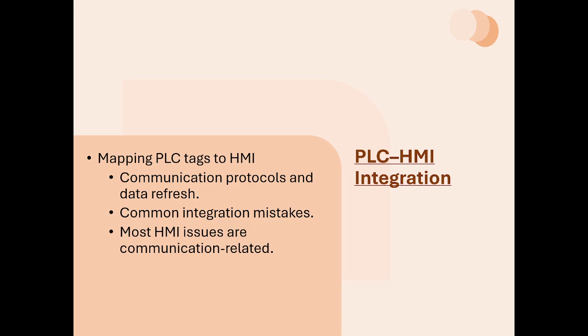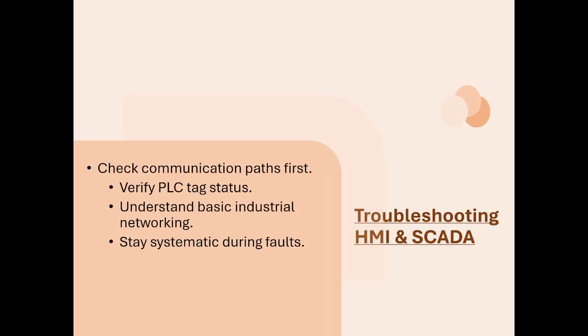Okay. Now, when that trust is broken, the next skill an engineer must rely on is troubleshooting. Now, troubleshooting is not about panic. It is about thinking clearly under pressure. So when something is not working on an HMI or SCADA system, experienced engineers follow a simple order. First, they check communication, then they check PLC status, then they check field signals. Okay? Now, SCADA, which stands for Supervisory Control and Data Acquisition, as I mentioned earlier, often sits on top of multiple PLCs and networks. So because of this, many problems appear on SCADA screens, even though the root cause is somewhere else. Now, good troubleshooting means asking the right questions instead of making assumptions. And once issues are resolved, engineers often reflect on how prepared they really are.